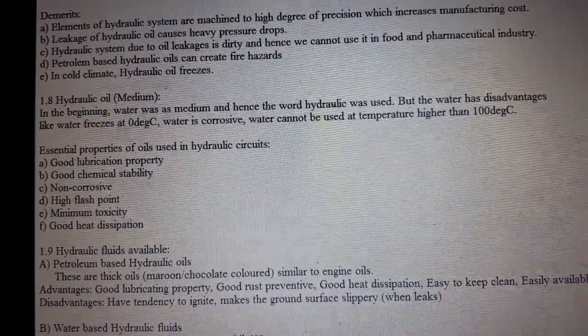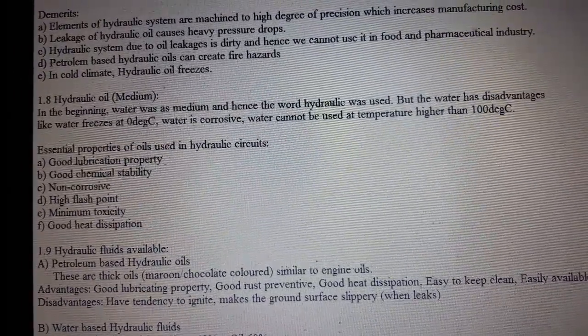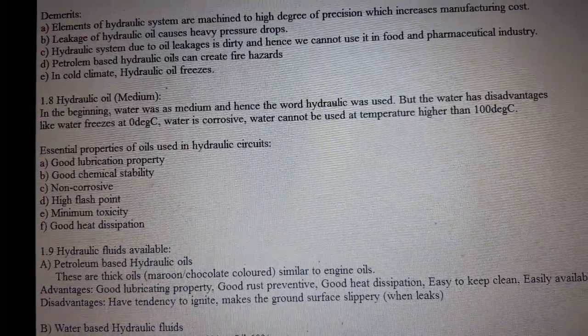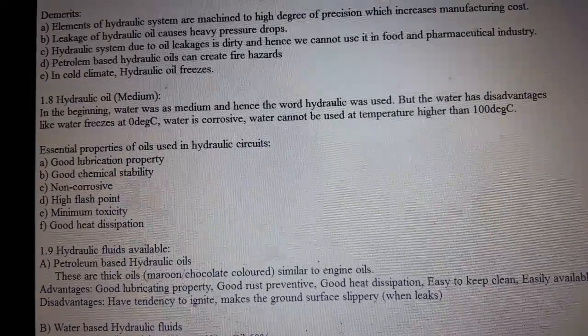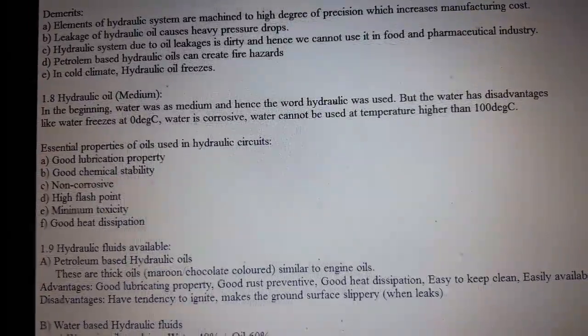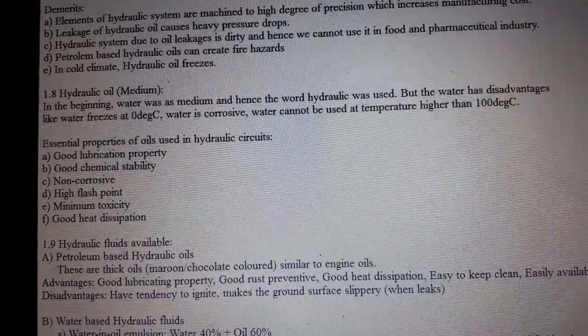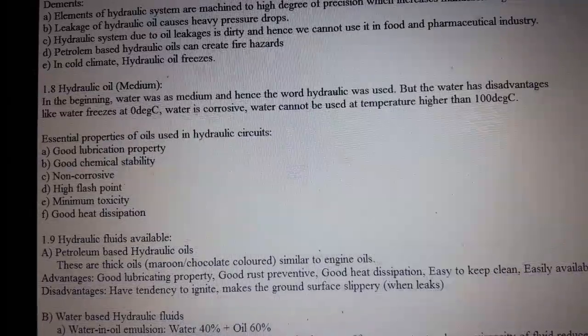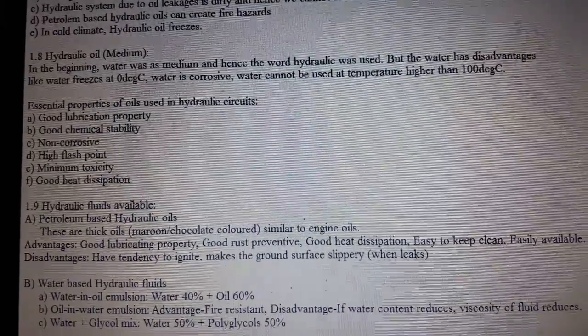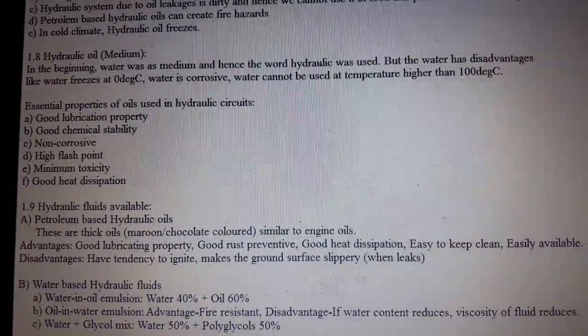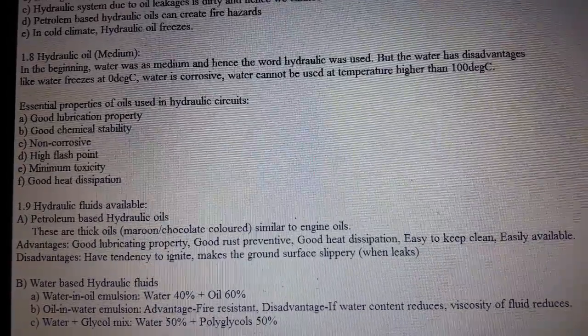Petroleum-based hydraulic oils can create fire hazards. In cold climates, hydraulic oil freezes. Hydraulic oil as medium: in the beginning, water was used as the medium, hence the word 'hydraulic.' However, water has disadvantages — it freezes at 0°C, is corrosive, and cannot be used at temperatures higher than 100°C. Essential properties of oil used in hydraulic circuits: good lubrication property, good chemical stability, non-corrosive, high flash point, minimum toxicity, and good heat dissipation.